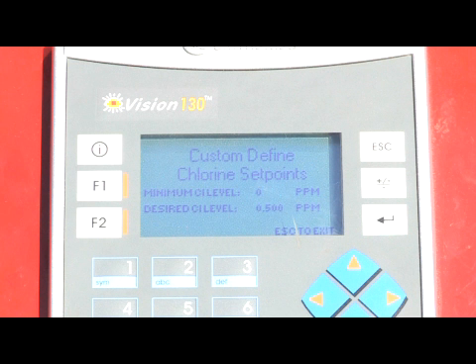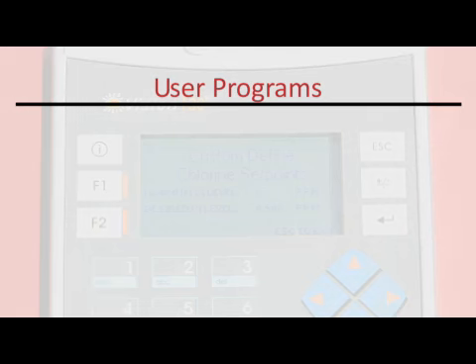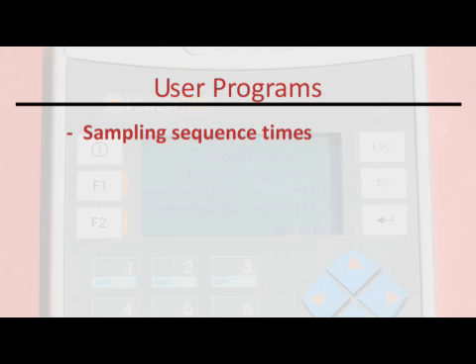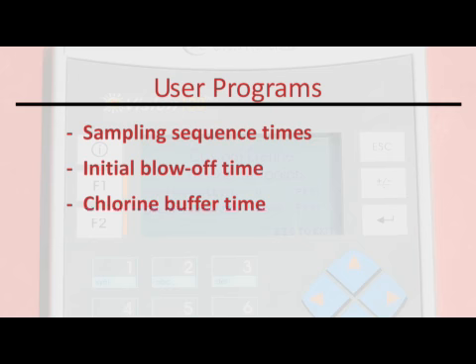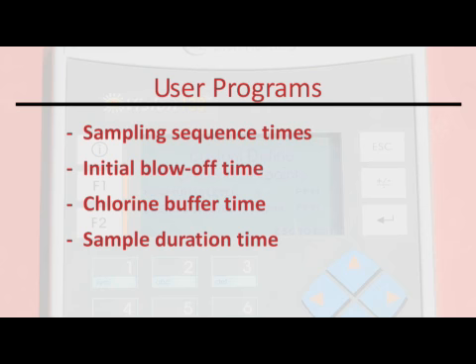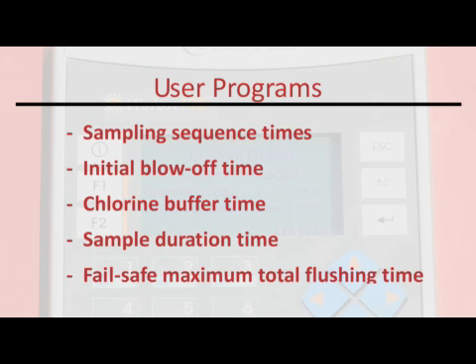Once the minimal and desired levels have been set, the user would program sampling sequence times when the unit will test residual levels. Additionally, the user would program an initial blow-off time, a chlorine buffer time which eliminates any possible errant readings, a sampling duration time — the length of time the unit will sample if above the minimum level — and a fail-safe maximum total flushing time.